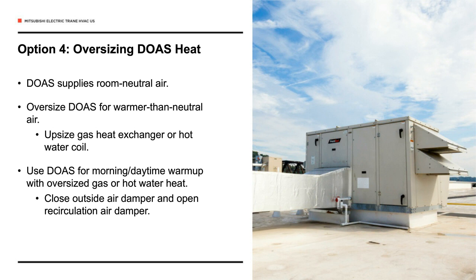Pretty easy to do. In the Midwest, most of the northern climates use gas heat for the heating source in DOAS. We do see some hot water heat. I believe that we'll see a migration as we see strategic electrification and all-electric building design start to take hold in places other than New York City and Boston and California. I think we'll see the DOAS systems gravitate from gas-fired heat to heat pump heat. So you can today select DOAS systems. Manufacturers can build those units with heat pump coils and heat pump condensing units built in. I think we don't see that many of those today. I think over time we'll see a gravitation towards the heat pump technology in the DOAS system also.